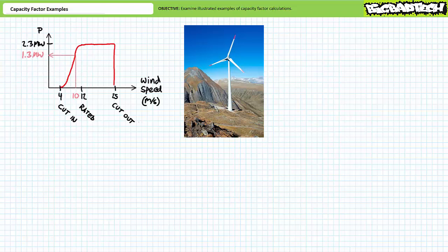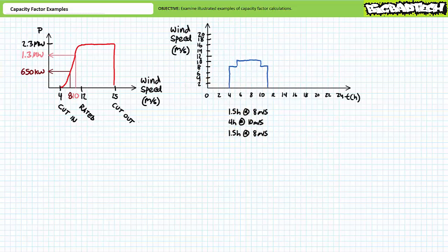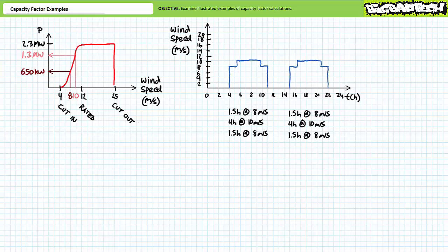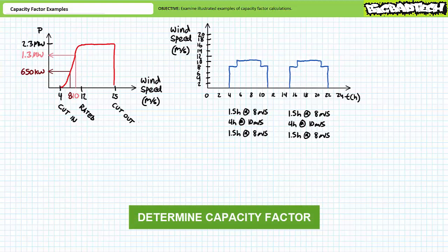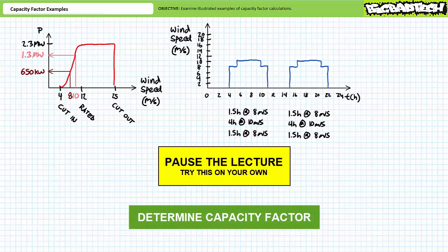Let's say this turbine produces only 1.3 megawatts at 10 meters per second, and output drops to a paltry 650 kilowatts at 8 meters per second. The turbine is installed in a mountain pass that regularly experiences the following pattern. Every morning, wind rushes down the pass at 8 meters per second for 1.5 hours, 10 meters per second for 4 hours, followed by another 1.5 hours of 8 meters per second wind. Every evening the phenomenon repeats in the opposite direction — wind rushes up the pass at 8 m/s for 1.5 hours, 10 m/s for 4 hours, then another 1.5 hours at 8 m/s. This pattern repeats every single day, nonstop, for one full year. See if you can calculate the capacity factor of this turbine — pause the lecture and try this on your own.